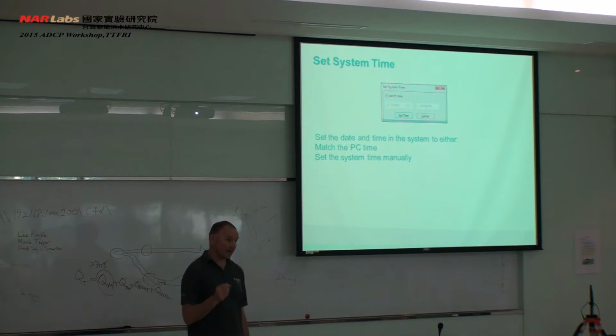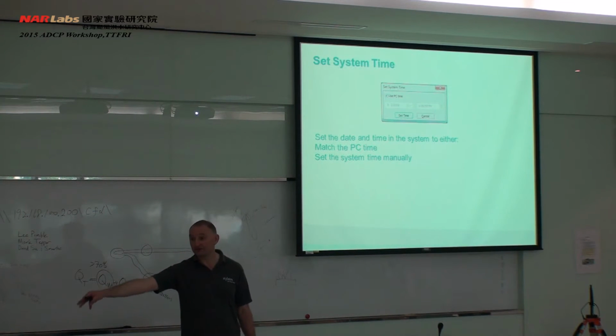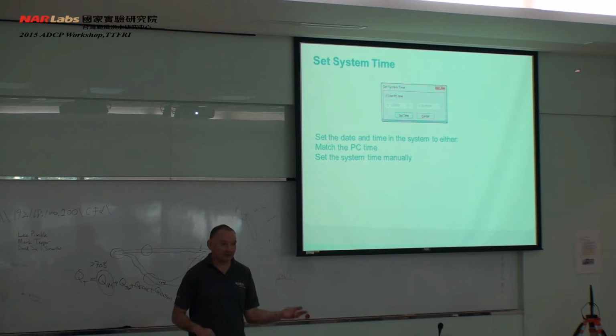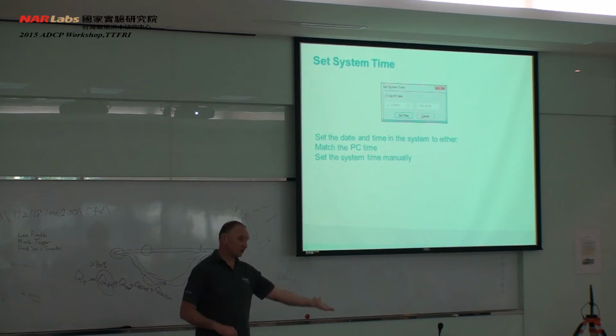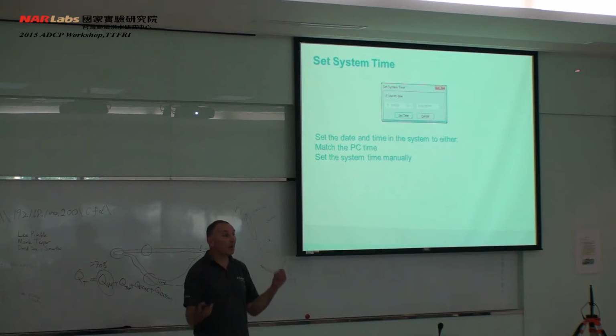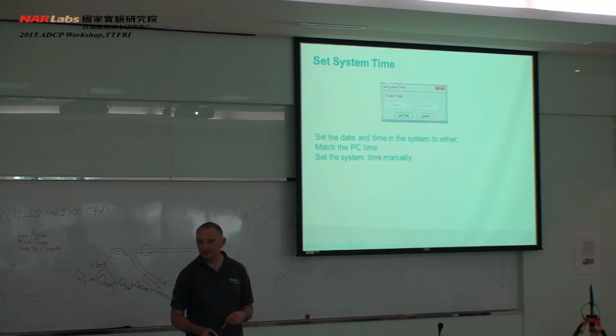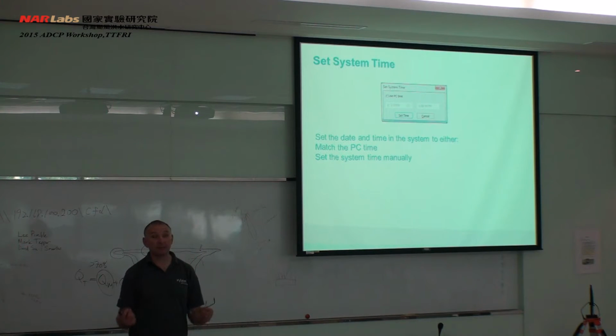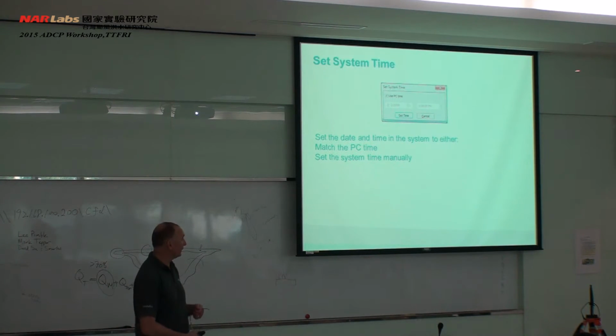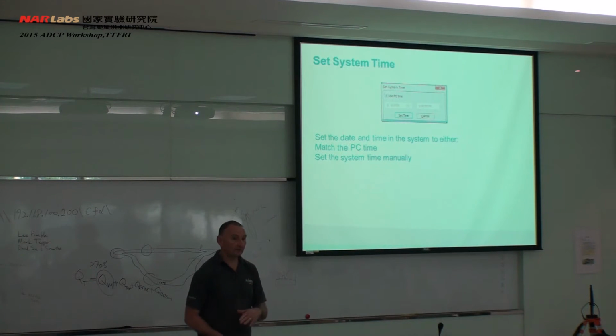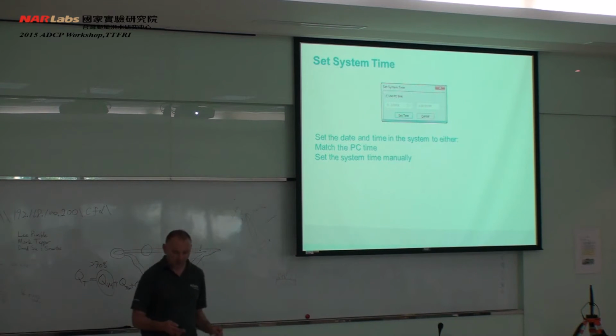The file name of the data that you collect, though, when we start a new file, the instrument automatically gives it a file name of year, month, day, hour, minute, second. It takes that time from the PC. So you might have a file that starts at 12:30 according to the PC, but in the UK, if it was in summertime, the instrument would say 11:30, an hour before, for GMT. So just be aware of setting that, and when you're looking for your data, particularly when you want to start inputting this data into external packages and tie data together, it's really important. The data time comes from the instrument, so set that instrument correctly.